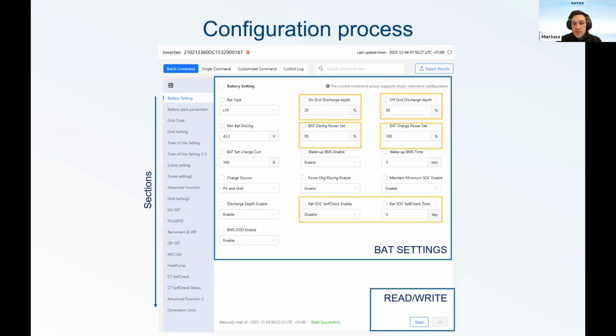Then the second case is the battery self-check. We can enable a battery self-check calibration after some days. The system will check whether the batteries were charged up to 100%, which is the calibration point, or not. If it was not charged, for example for 14 or 20 days, the system will charge from the grid to perform the battery calibration. And the last is the read and write button. We can read the values quickly and then set them up.